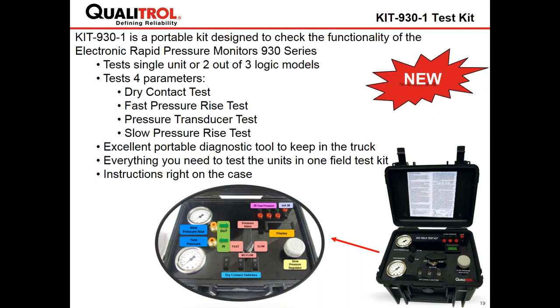Now let's move on to the Kit 930, which is used for the Electronic Pressure Monitor Series 930. This is a brand new kit which we have recently launched. It can be used on the 930 series, and it's a portable kit designed to check the functionality and parameters that we have to test. So this can be used for a single unit or the 2 out of 3 logic models which I mentioned earlier.